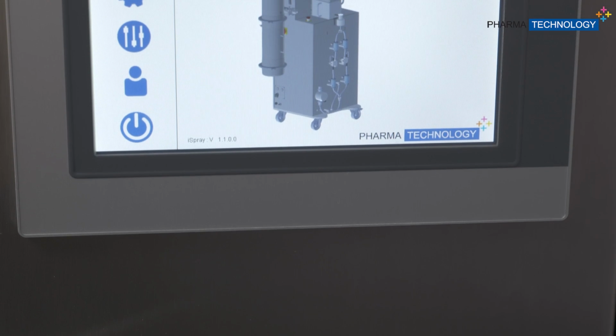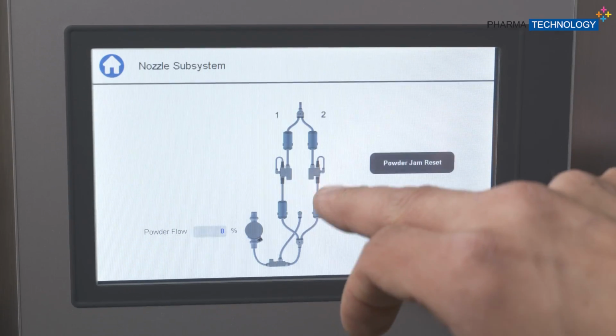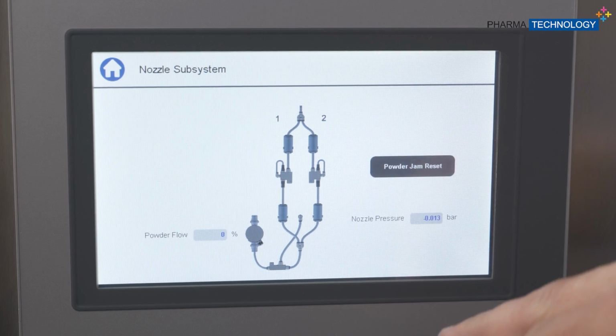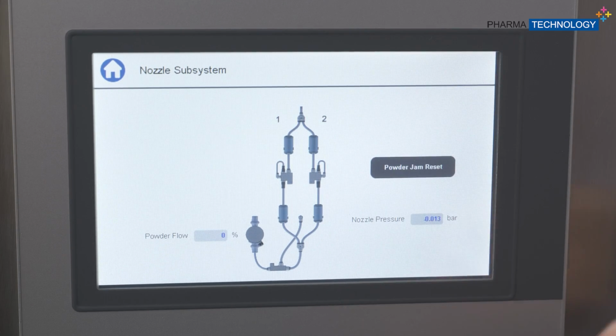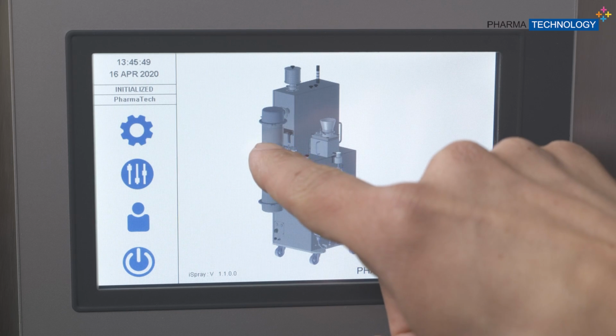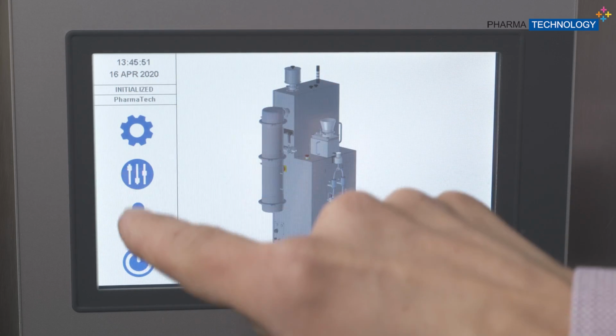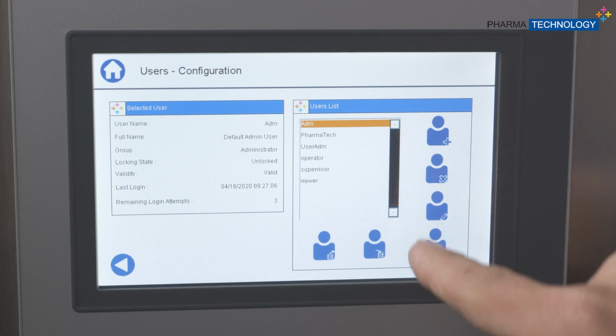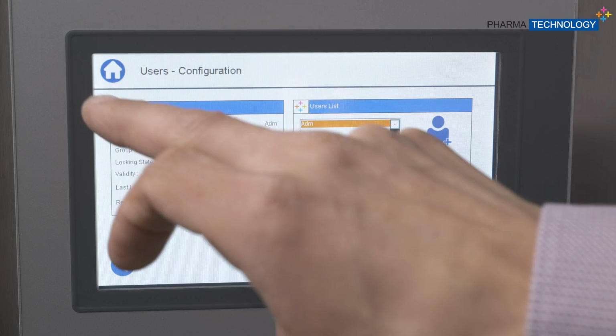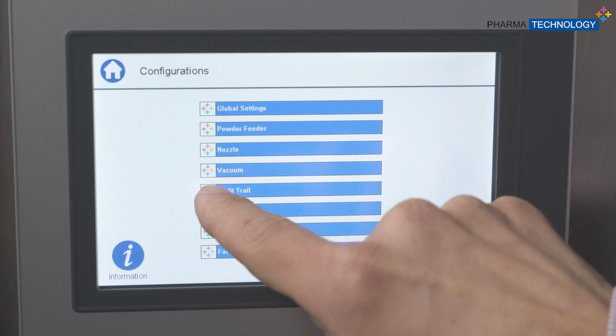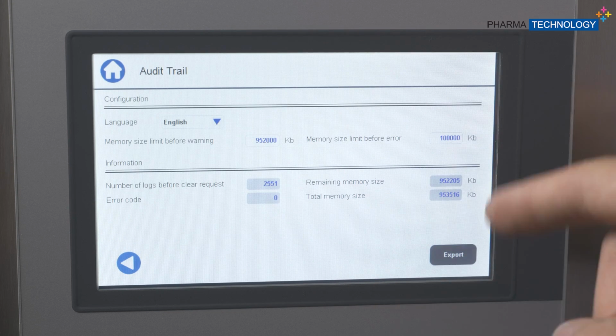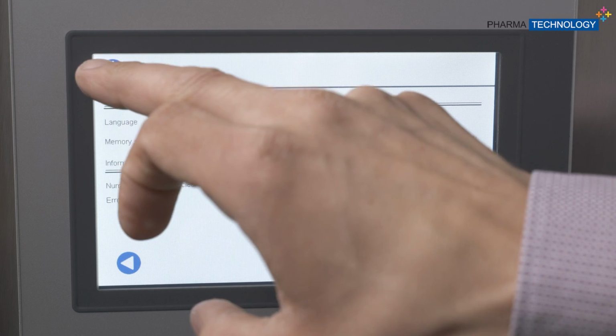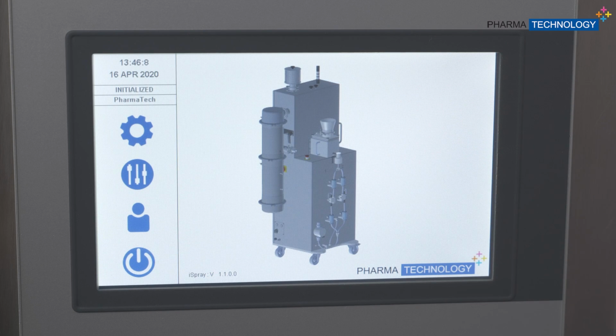The software we created for the iSpray is CFR 21 Part 11 compliant, very graphical and easy to use. Here we have the display of what is happening on the machine and which sides we are using, as well as the state of the vacuum. We also have user management with different users and different levels of access, and last but not least, audit trail functionality with possible exports and reports. Finally, we also have customizable OPC UA communication to communicate with centralized systems, other presses, or other systems.